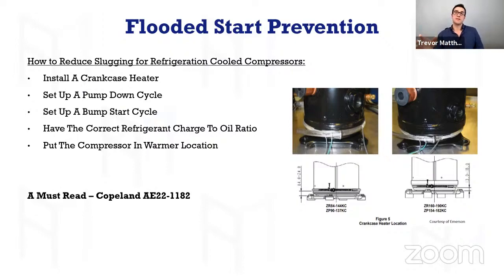Do a bump start cycle. A bump start cycle, there are different components out there where, if the compressor's been off for longer than 5 or 6 hours and the ambient is a certain temperature, it'll start the compressor up for 2 seconds and then shut it off for 15. Start it up for 2 seconds, shut it off for 15, and so on. Different manufacturers have different times, but what happens is it flashes the gas. So instead of having a slug, you'll have more of a small flooded start happening to boil off that liquid refrigerant.